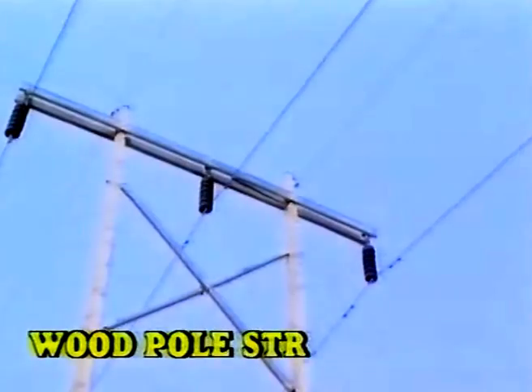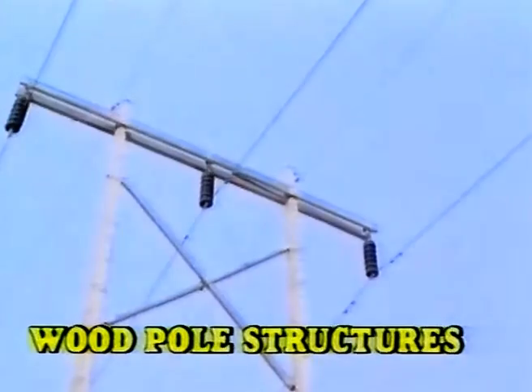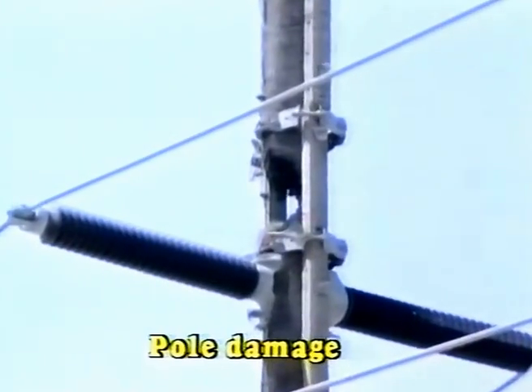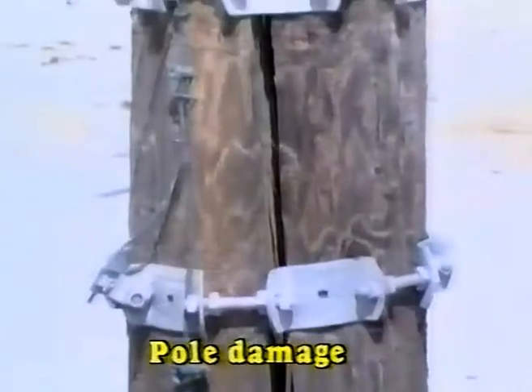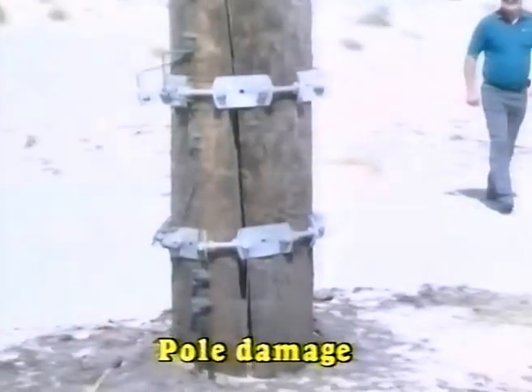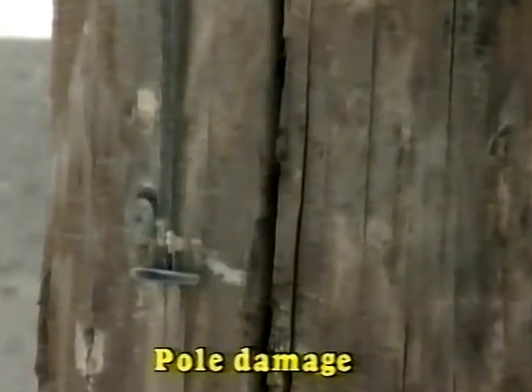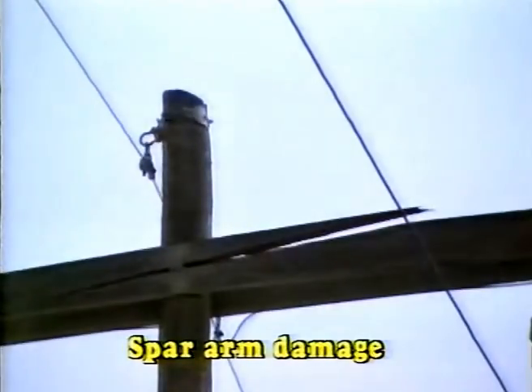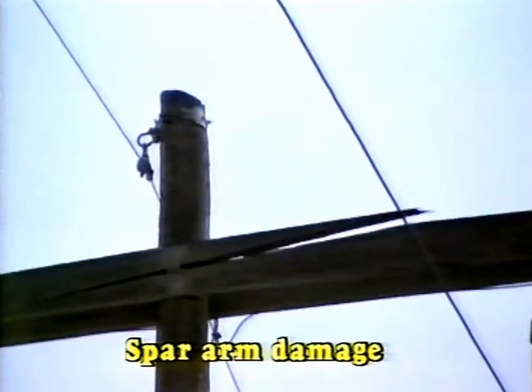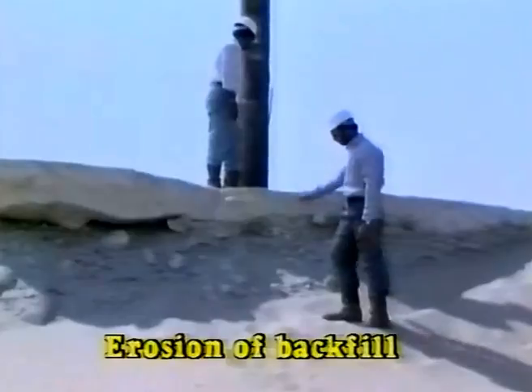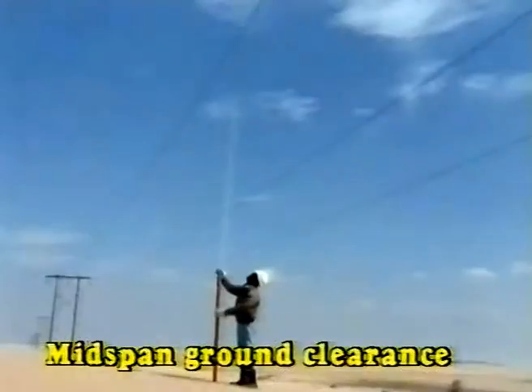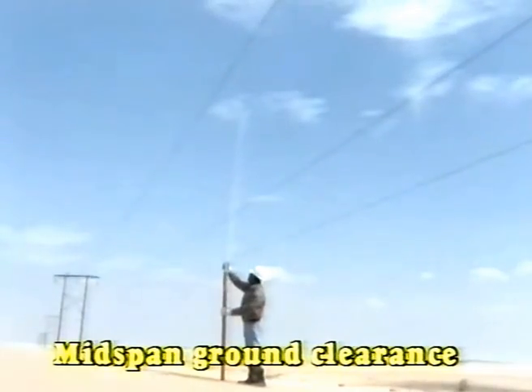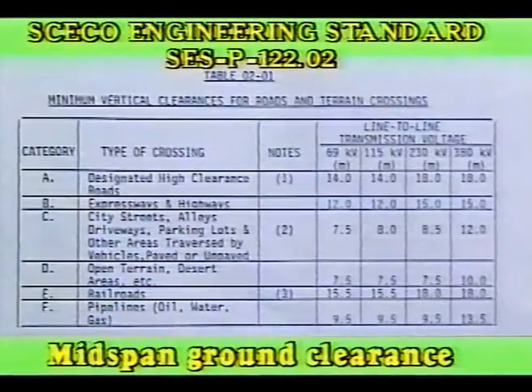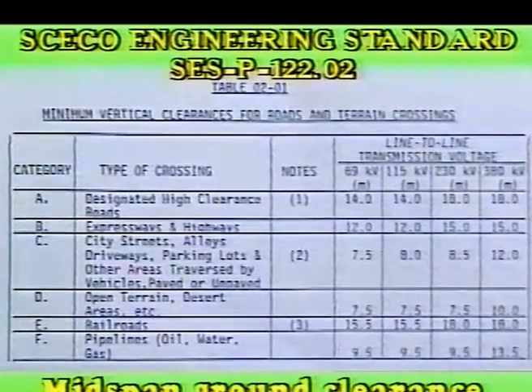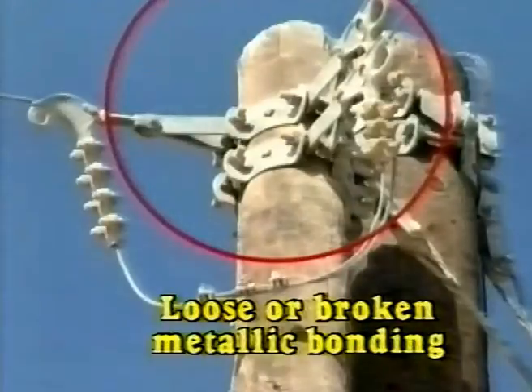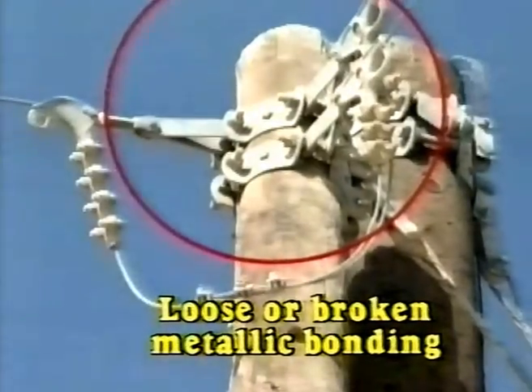As in steel structures, wood pole structures must also be inspected for pole damage like fire or lightning damage, as well as rot, termites, cracks. Spar arm damage. Look for cracks, deterioration, or fire damage. Erosion of backfill and other movement. Mid-span ground clearance. Minimum ground clearance should be in accordance with this table. Loose or broken metallic bonding and grounding as in shield wire and structure.